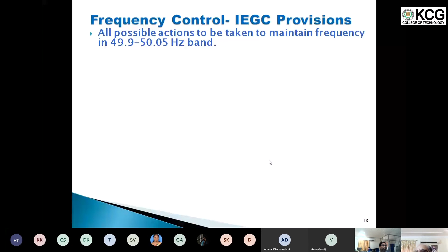These generators are required to set their governors in such a manner, because with these rotating machines you have inertia available, and you also have a limit, what is called valve wide open operation, VWO. When you have a generator of, let's say, 500 megawatt thermal, you will have 5% of that extra available, where it can pick up 5% of its rating if required. If a generator trips, then the frequency will tend to go down, and the governor will act and inject more power. Then the generators will pick up the load to bring it back to the nominal frequency.